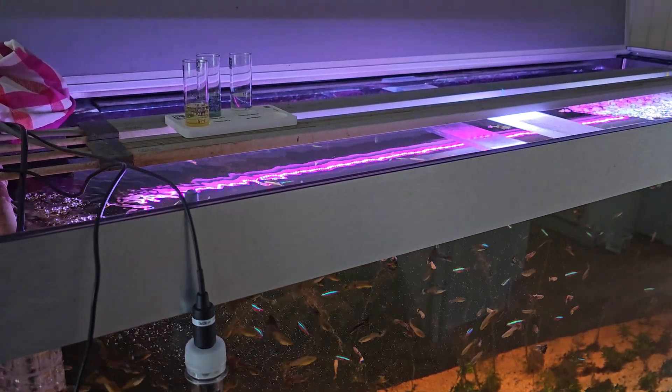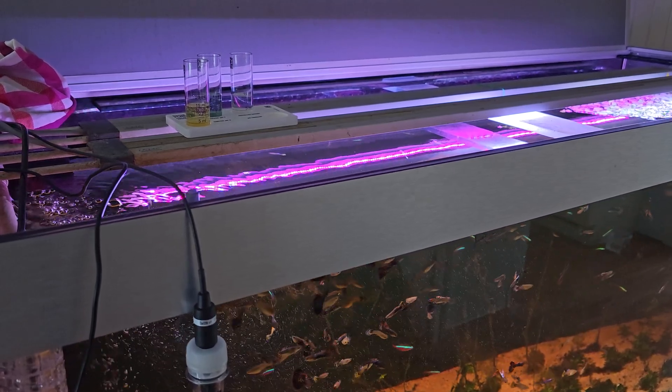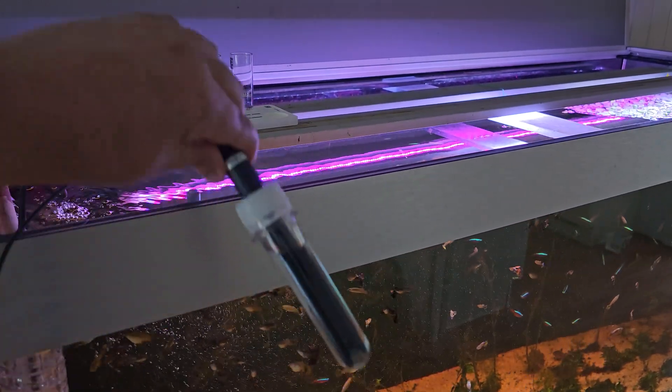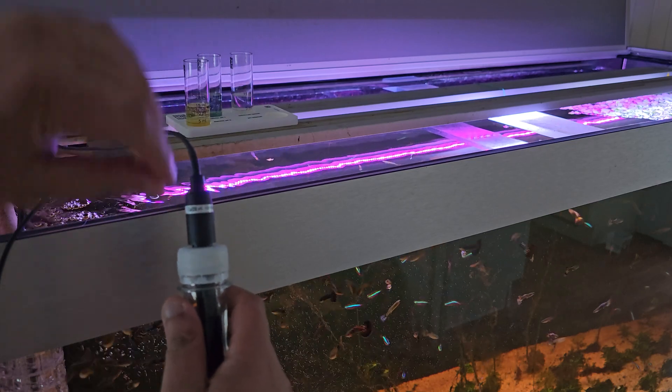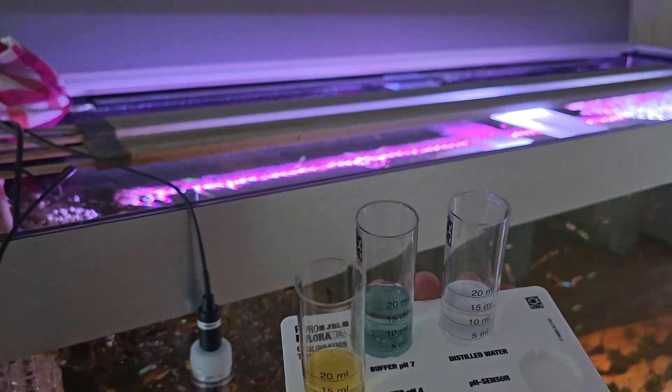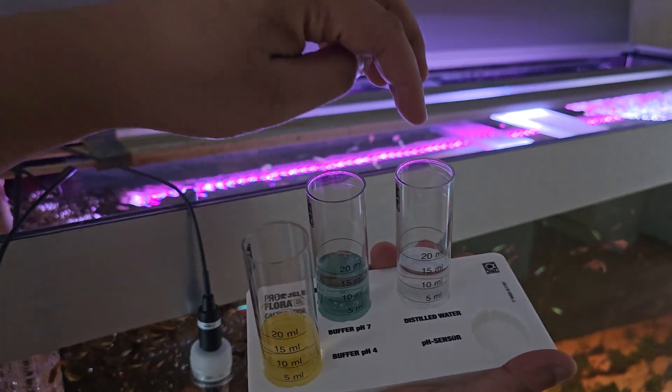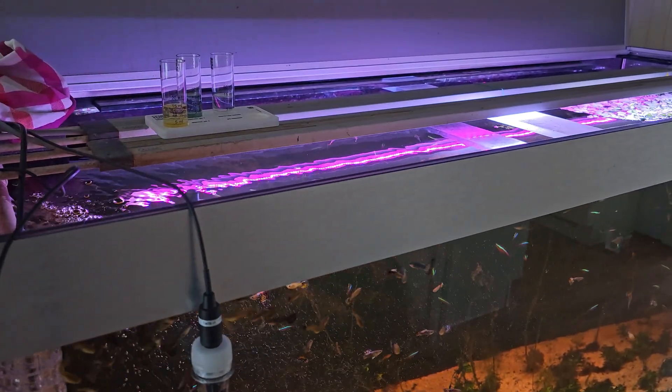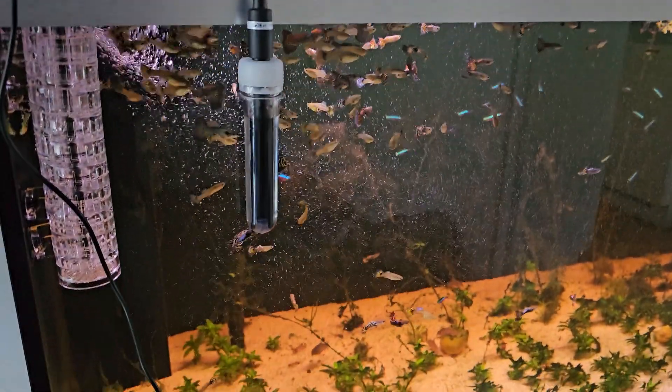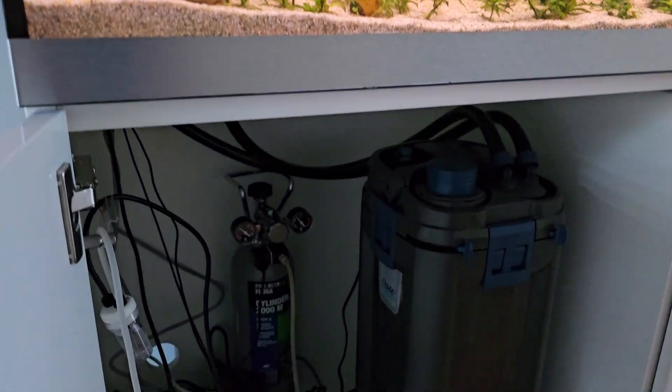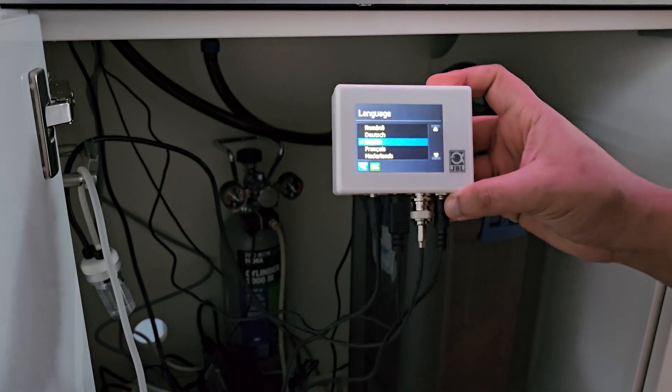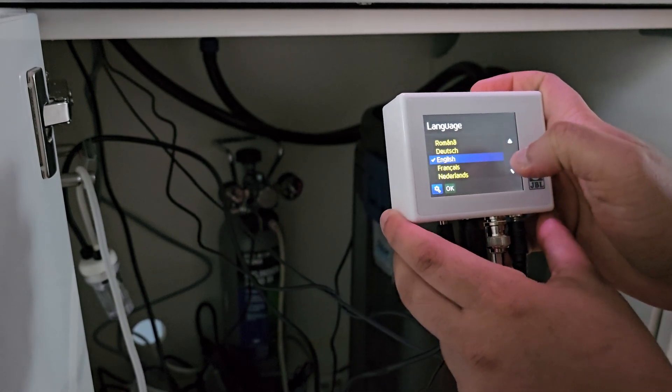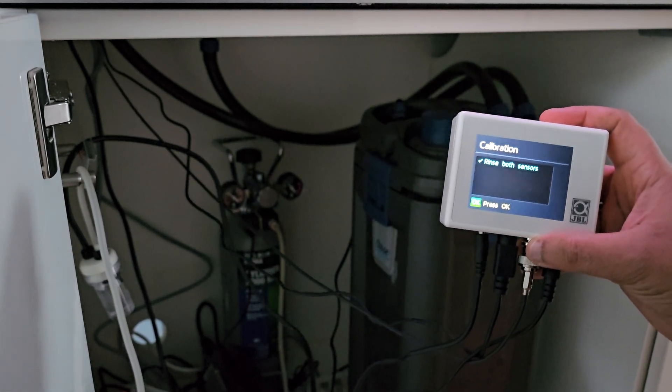And I'm back. So what I'm gonna do now or attempt to do is calibrate the sensors. This is the temperature sensor and this is the pH sensor. It's in liquid, it's supposed to stay wet, so I'm gonna put it out and put it in these three fluids here: pH 4, pH 7, and distilled water for the rinsing. Also down here is the display box. So let's put it on English, start calibration. It says rinse both sensors, so that's what I'm going to do.